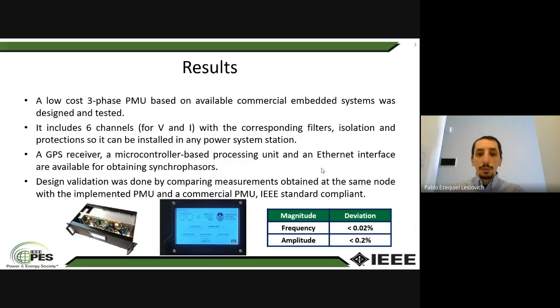Based on available commercial embedded systems such as ARM microcontrollers, a low-cost three-phase PMU was designed and tested. The design includes 3 voltage measurement channels and 3 current measurement channels, with the corresponding isolation and electrical protections, a GPS receiver providing the timing signals, a microcontroller-based acquisition and processing module, and an Ethernet interface for synchrophasor transmission over Internet.